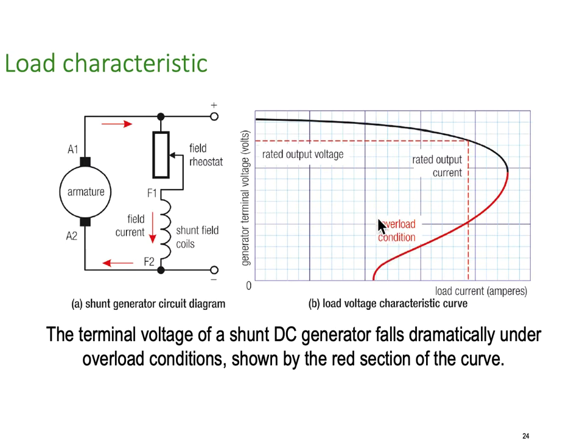So the load characteristics for a shunt generator look like this. And you might expect that here's the standard curve we saw on our previous generator. Once we reach full load, then as the load gets past full load, the voltage drops off. And if you overload it, the speed drops back and the voltage at the terminal keeps slowing down and down until it stops. So this is why it wraps back on itself.